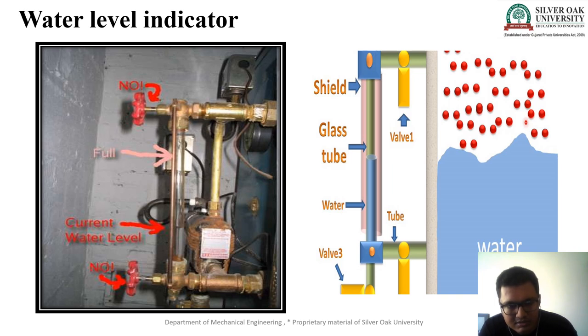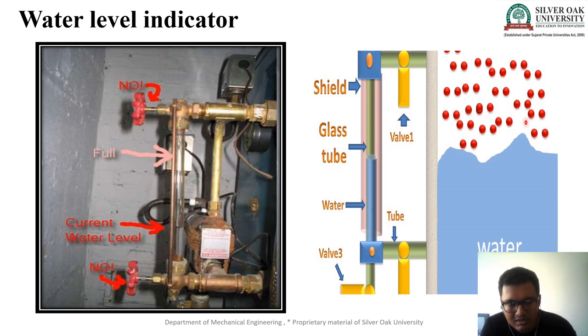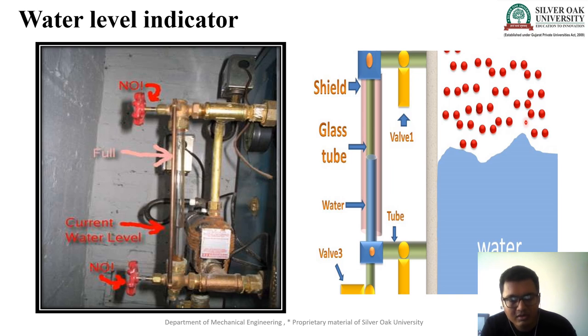When both valves are open, water gets inside the glass tube from below and steam enters from the top. After a certain time it reaches equilibrium and shows the water level inside the glass tube. It is compulsory to know how much water is present inside the boiler, because if water is not available and we supply heat energy, the boiler gets overheated and an explosion may occur.